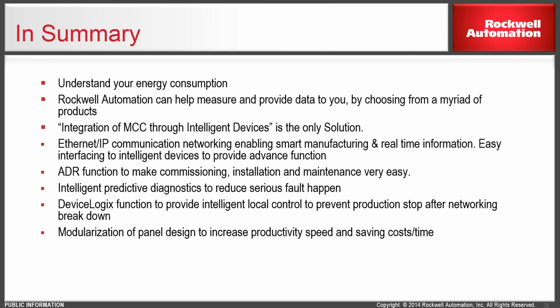DeviceLogix function - as I mentioned, in case of a network breakdown, you can directly control through the component level and the operator station, and device logic functionality is also there. So in case of failure, you can directly configure the parameters without the network. Modularization of panel design also helps increase productivity and speed, and saves significant cost and time.